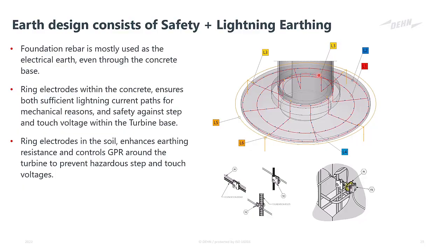Inside the turbine, L3, we have something like this. We call these yellow points or fixed earth terminals, and these are connected to the reinforcing and the earthing system, and they're concealed when the concrete is poured, so they sit flush with the concrete on the inside, and you can attach anything like an earth bar and things like that to the earthing system directly for inside the turbine or inside buildings. And you can see some examples here of connections made from conductor to the reinforcing by using clamps, lightning protection tested clamps, and how this would be implemented.